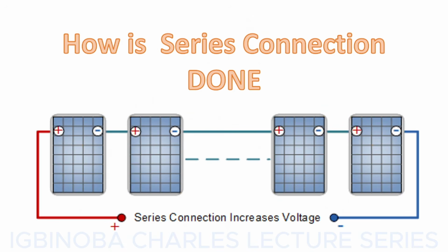How is series connection done? When solar panels are wired electrically in series, as you can see we have about four panels here. The first terminal, the positive terminal, is left alone. Then the second terminal of the first panel, which is negative, is connected to the positive of the second panel. The negative of the second panel is connected to the positive of the third panel. The negative of the third panel is connected to the positive of the fourth panel. You continue this connection until you get to the last panel, where you have your negative and leave it hanging. So this is your positive probe and this is your negative probe.